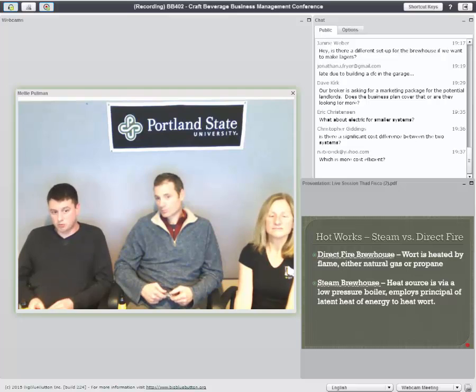For low NOx, you can expect to spend an additional 50% for the boiler. For ultra low NOx, it can be an extra 100%. So we'll find that in Southern California there's a lot of direct fired systems. Ironically, it's worse for the environment, but the state gives it the stamp of approval. So, which is more cost efficient? Natural gas is not that expensive when you're talking about a $20,000 swing in price.